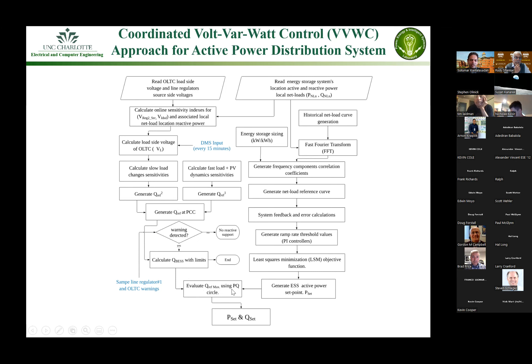One aspect is coordinating with the battery energy storage and the regulators. With effective coordination of reactive and active power, the number of tap operations on the regulators is reduced. We try to capture that as a dollar value, but it's not a big value, because the number of tap operations and tap failure life cycle isn't typically significant, though it can become a big value with high renewable energy intermittency.